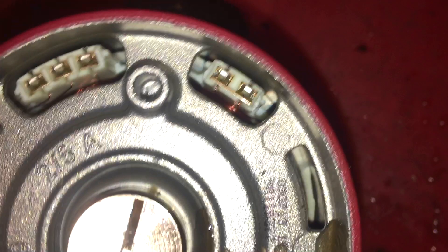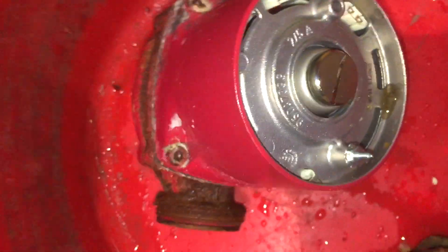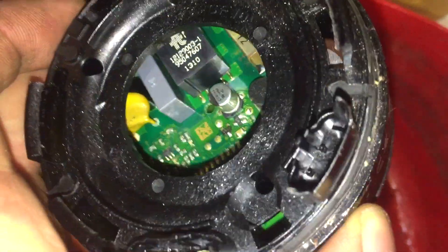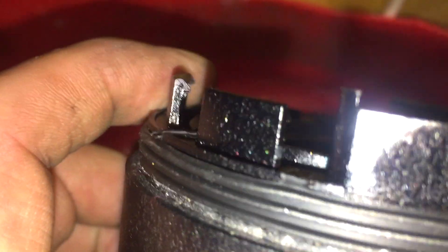There are two connections on there — one three-wire, one two-wire — but on the underside there's only a three-wire; the two-wire connector isn't populated. It's designed to be pulled apart, so on these you could pull this head off and bleed them. Obviously they can't be running, but you could bleed them.